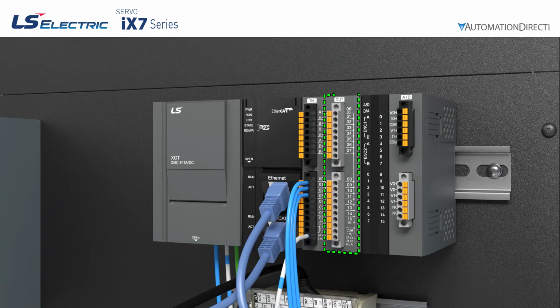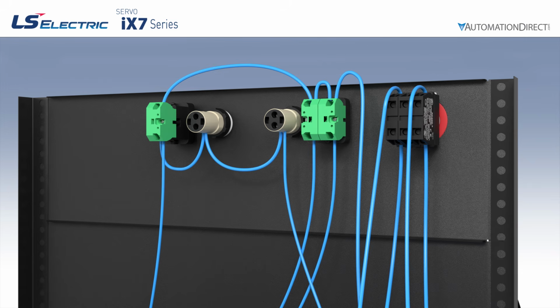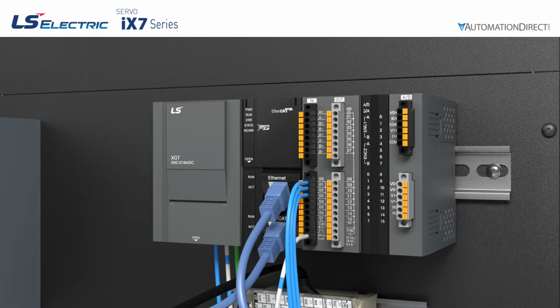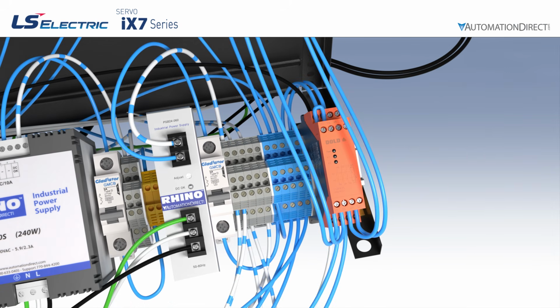The XMC digital outputs are sinking outputs. The 24-volt I/O supply is connected to the positive side of all three indicator lights and to the controller's output module positive terminal. The red indicator is connected to the DO1 terminal, the blue indicator is connected to the DO2 terminal, and the green push button indicator is connected to the DO3 terminal. The controller's 0-volt common is also tied to the I/O power supply common.